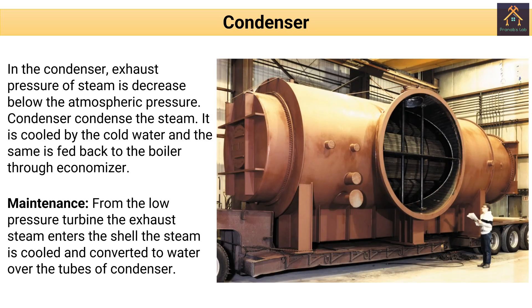Next, the condenser. In the condenser, the exhaust pressure of the steam is decreased below the atmospheric pressure. The condenser condenses the steam — it is cooled by cold water and the same is fed back to the boiler through the economizer. From the low pressure turbine, the exhaust steam enters the shell where it is cooled and converted to water over the tubes of the condenser.